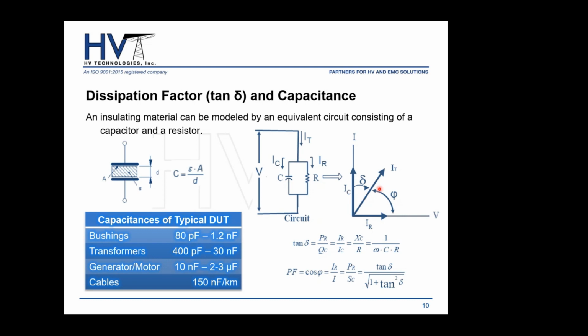As you can see at the bottom, there are some formulas that will do the conversion between tan delta and power factor if necessary. But basically, that is what we're looking for. We're looking for this deviation of the total current due to the effect of your resistive current. So some typical capacitances of some devices: bushings will have anywhere between 80 picofarads to 1.2 nanofarads. Transformers from 400 picofarads to 30 nanofarads. So with the MIDAS, you can basically test any bushing or transformer.